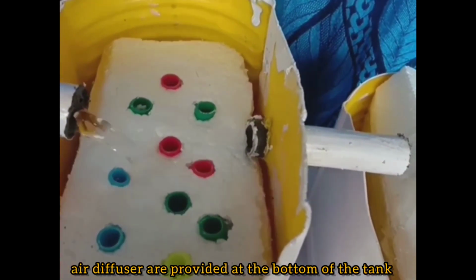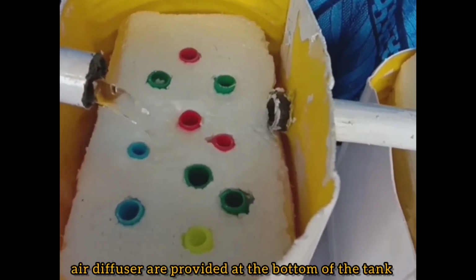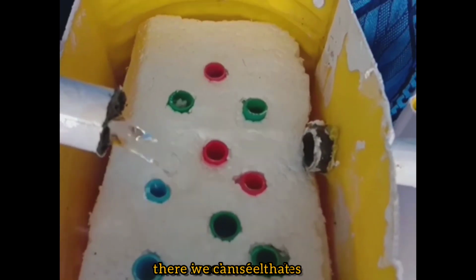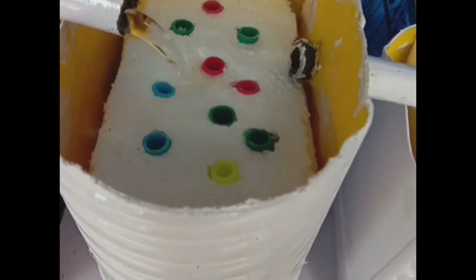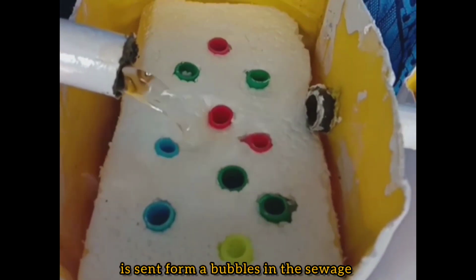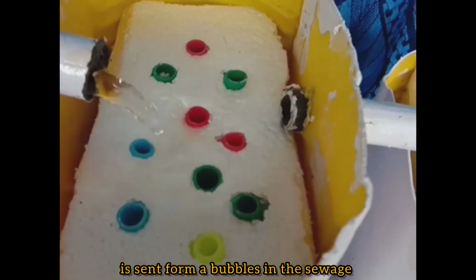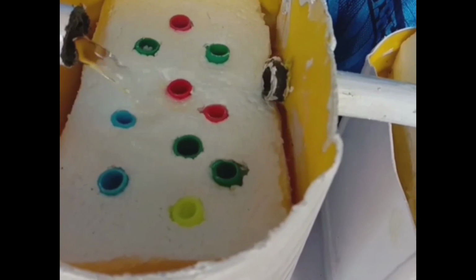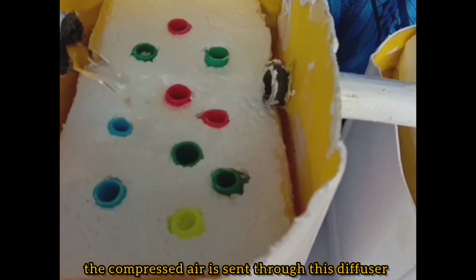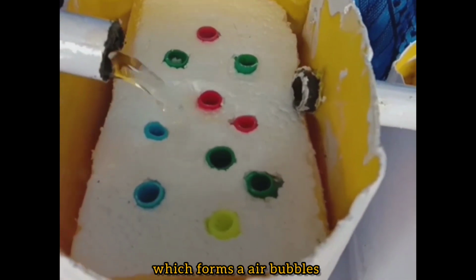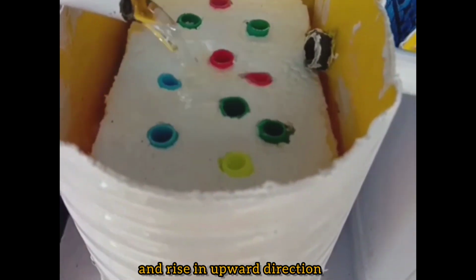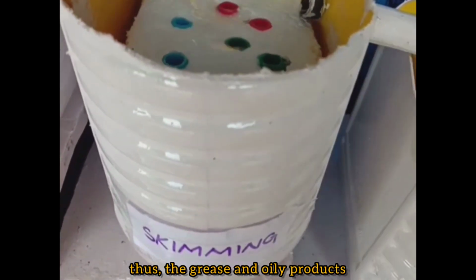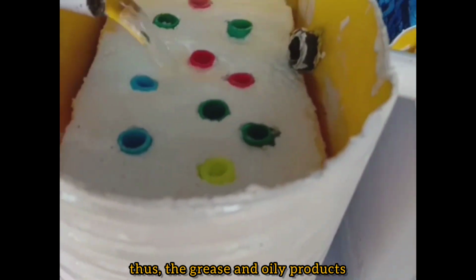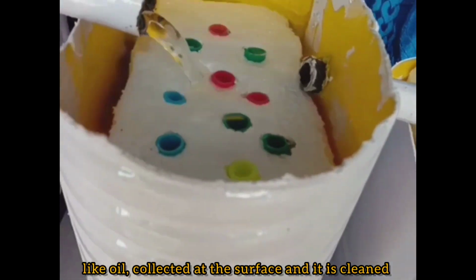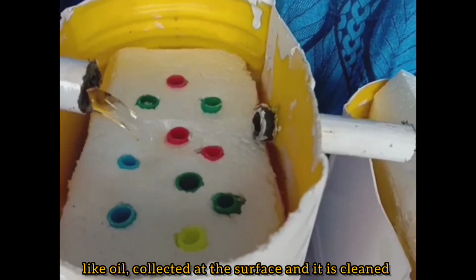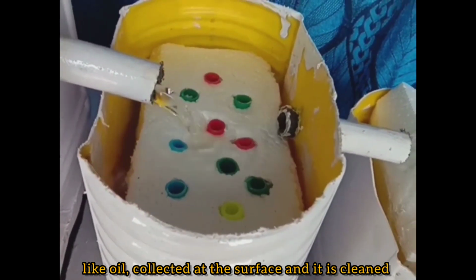Air diffusers are provided at the bottom of the tank. Here we can see colorful holes through which compressed air is sent to form bubbles in the sewage. The compressed air is sent through this diffuser, which forms air bubbles that rise in an upward direction. Thus, the grease and oily products collect at the surface and are cleaned manually or mechanically.